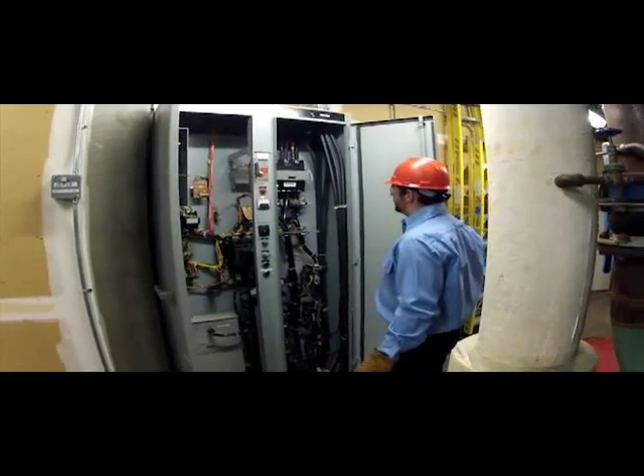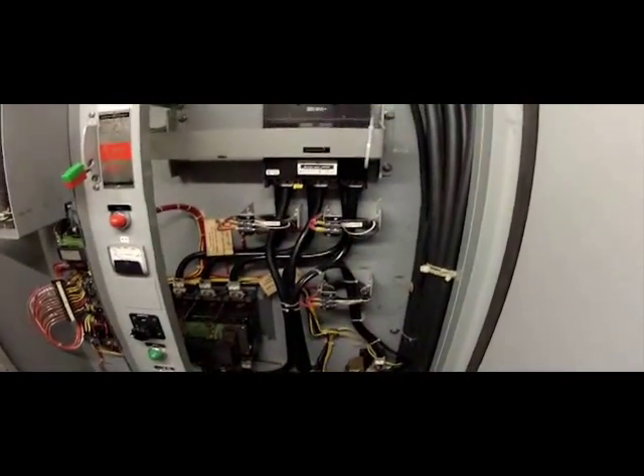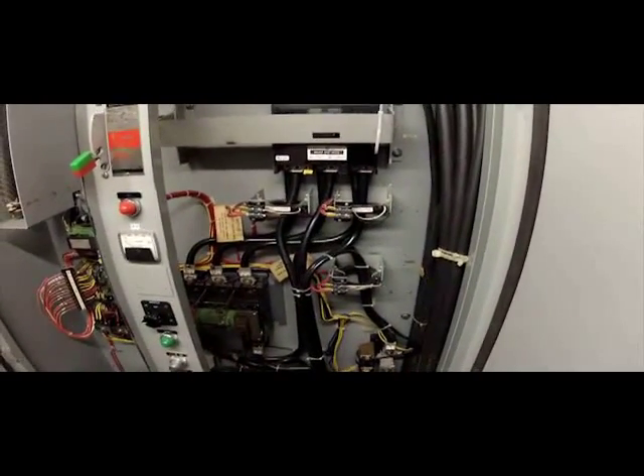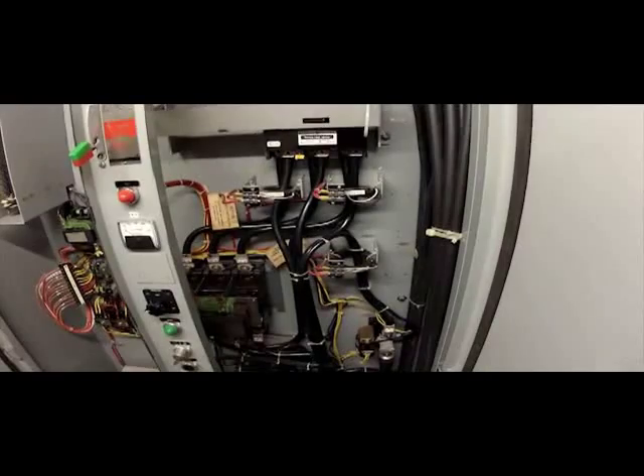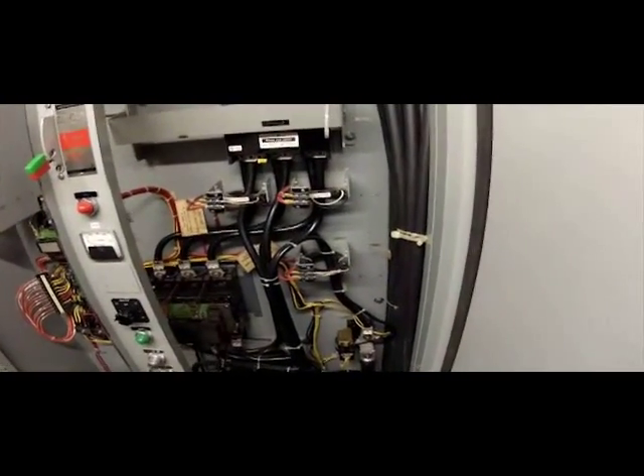Okay, so as you can see inside the cabinet, we've got on this side of the disconnect all three phases going to our machine. In these three phases, we have two wires on each phase. This makes it difficult to get around these wires in order to monitor because they're so bulky and they're spread apart a little bit.